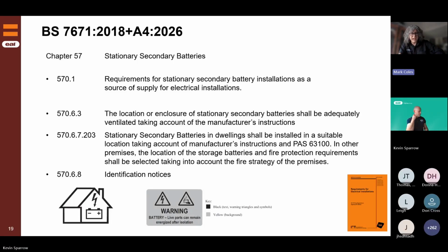What went into the PAS, now brought into 7671, is: don't install your batteries in stairwells, don't install them on escape routes, keep them somewhere as innocuous as possible, and don't put them in lofts either, because that's another issue. They should be ventilated, because some batteries can emit gases and you need fresh air to clean that out. So there's a lot to think about there.